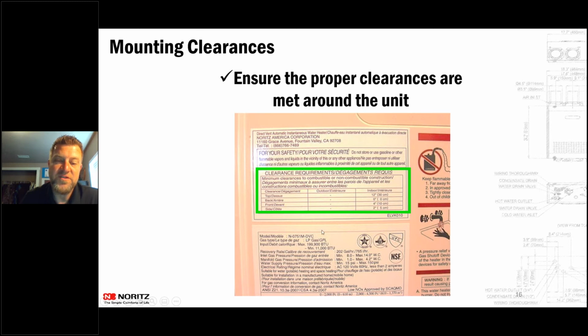So a lot of these units will show what the clearances need to be for the unit itself. Mounting it on the wall, it's also in the install manual as well. So make sure you pay attention to those. So like for this unit right here, off the top of it, they want to have a clearance of at least 12 inches off the top. Off the back, there's a 0 clearance. Off the front, they want at least 4 inches, and then to the sides, 2 inches.